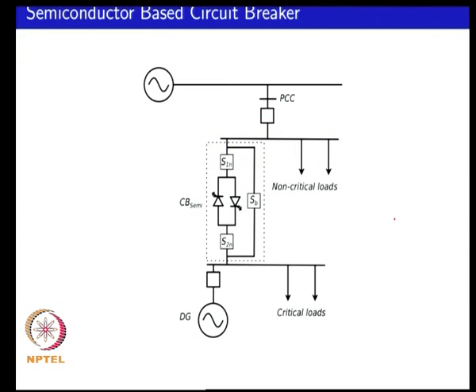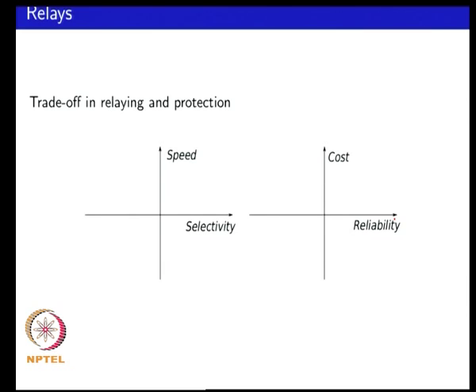If you look at the attributes of a protective device, you are looking at one that operates at high speed — it is capable of making decisions rapidly. You would also like to have selectivity, in the sense that if a relay is deciding whether to trip or not, it should trip where it is necessary. For example, if you have a fault in the zone of protection it has to trip, whereas if the fault is outside the zone it should not trip. It should be tripping for the right reason.